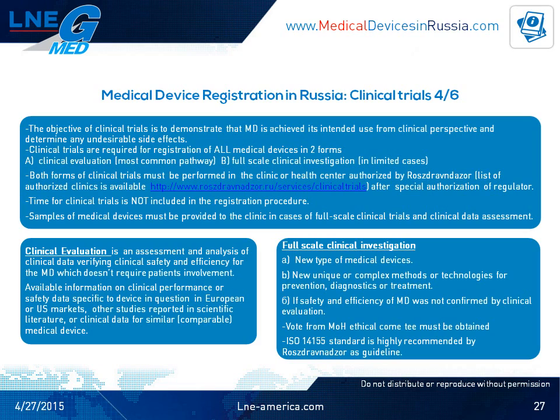Full-scale clinical investigation with patient is required by regulations in limited cases. These cases are the new type of medical device, new unique or complex methods or technology for prevention, diagnostic or treatment, or in case when safety and efficiency of the medical device was not confirmed by previous procedure, by clinical evaluation. For full-scale clinical investigation, vote from ethical committee must be obtained to start clinical trials, and ISO 14155 standard is highly recommended by Roszdravnadzor as a guideline to conduct clinical trials with patients.